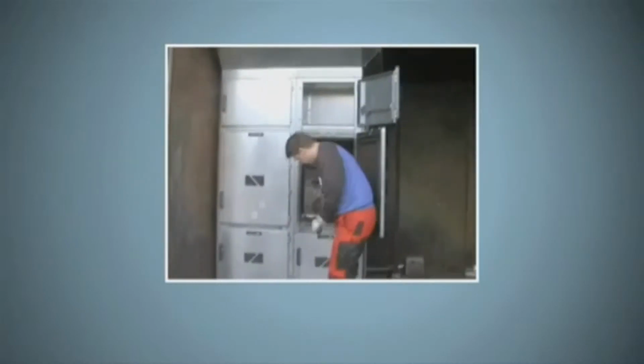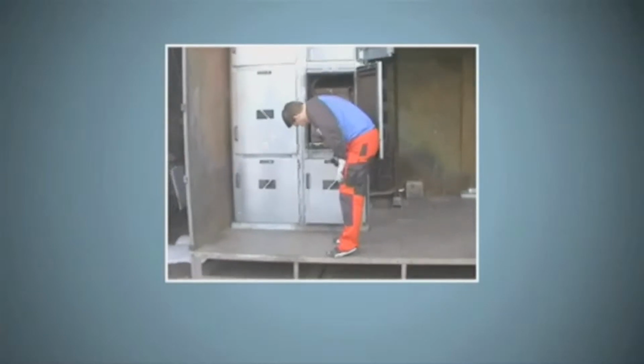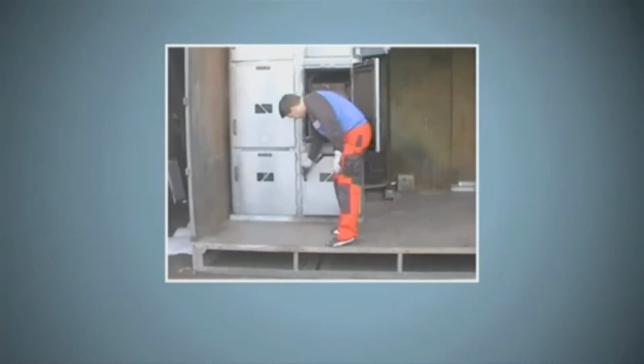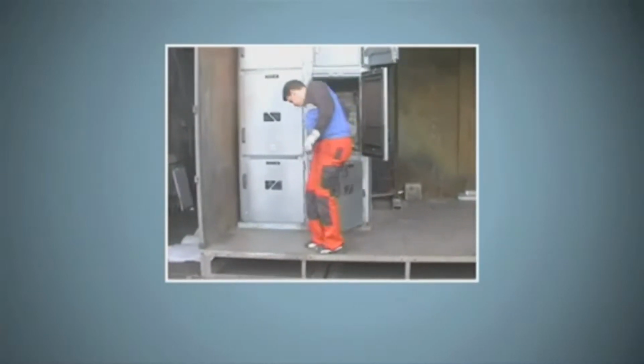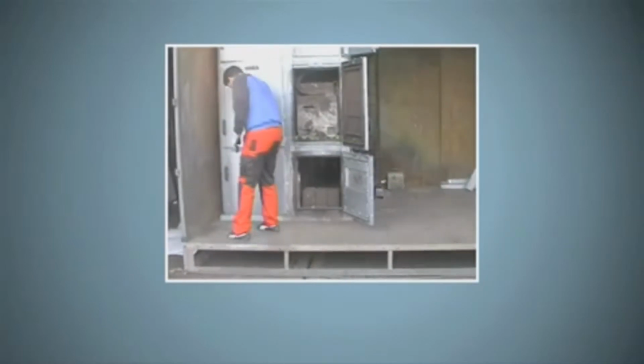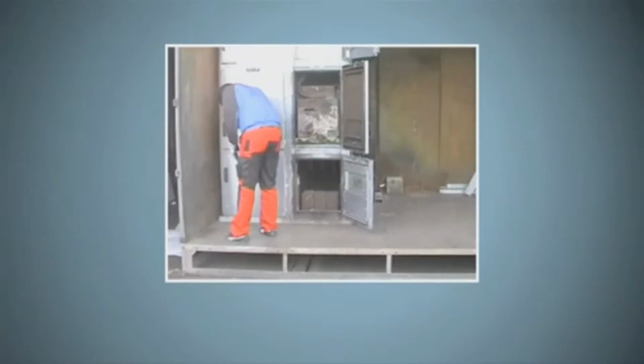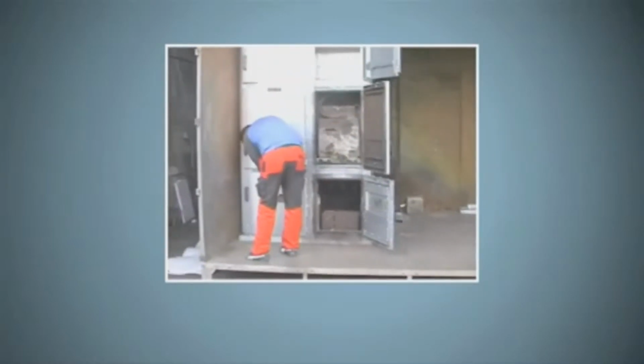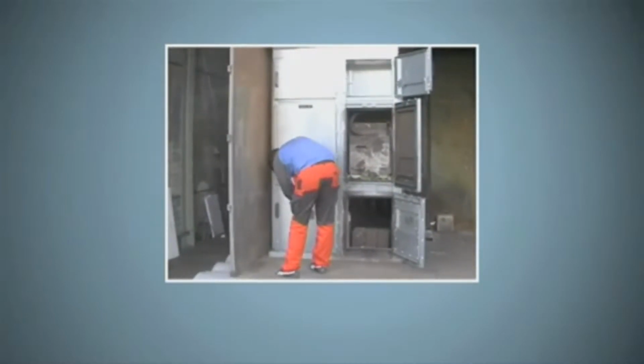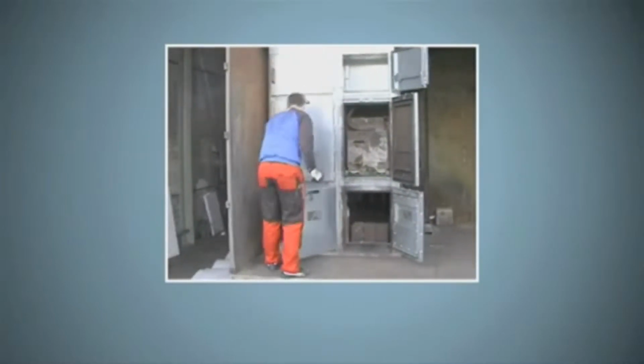Each panel is made up of a series of compartments equipped with sidewalls. The special design provides an 8mm air gap between two neighbouring panels in the unlikely event of an internal arc. This design assures that the damage is limited to the panel where the fault occurred.